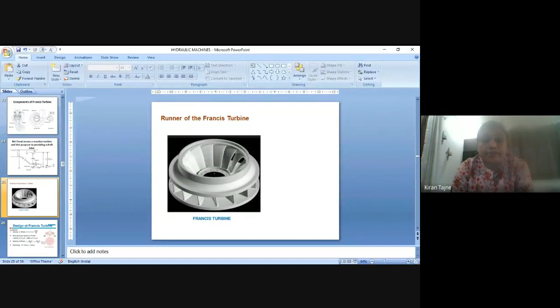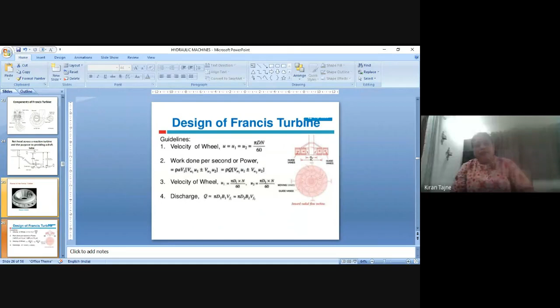So there are some guidelines for the design of a Francis turbine. The velocity of the wheel is calculated by the same formula, pi D N upon 60. Then the work done per second, or power, is calculated by the formula rho Q (Vw1 u1 minus Vw2 u2), where Vw1 is the whirl velocity at the inlet, u1 is the velocity of the wheel at the inlet, and Vw2 is the whirl velocity at the outlet. The wheel velocities u1 and u2 you can calculate by the formula.